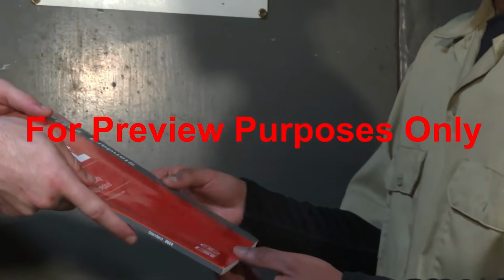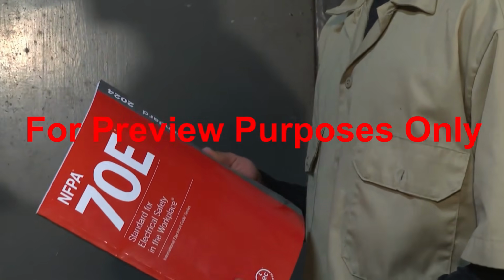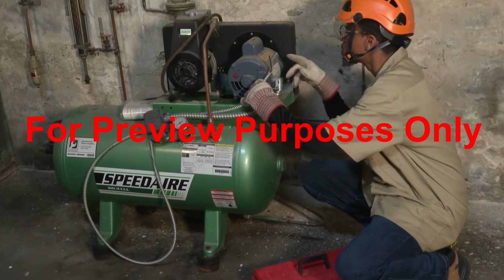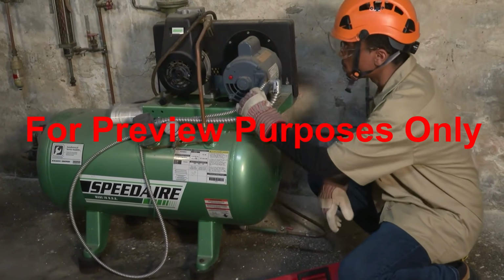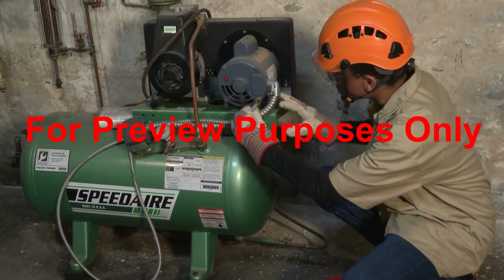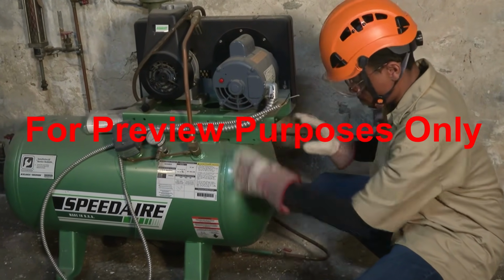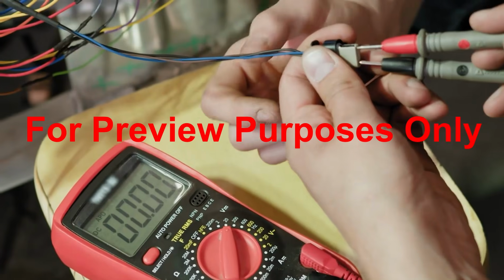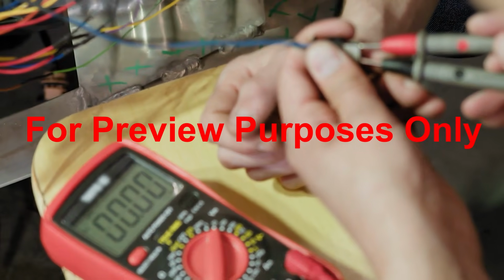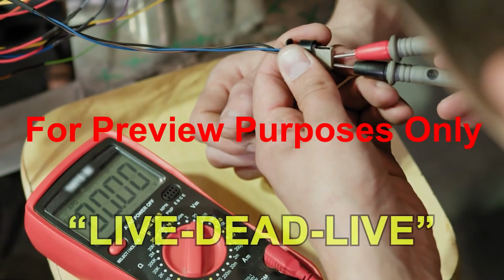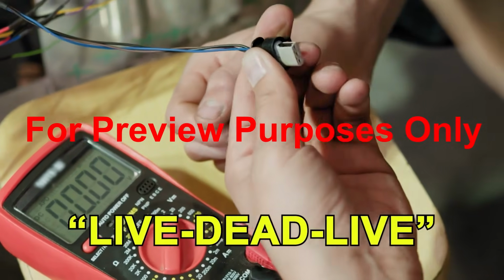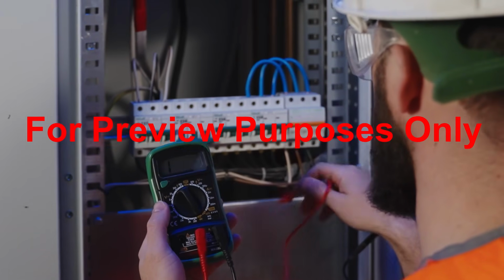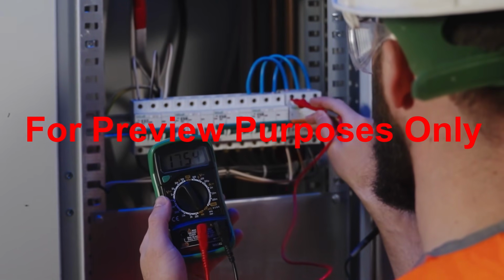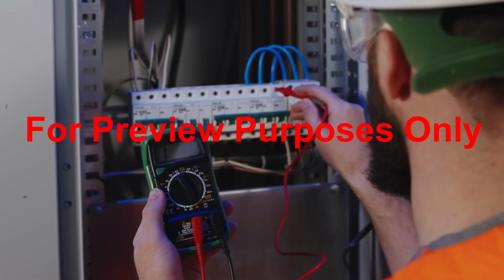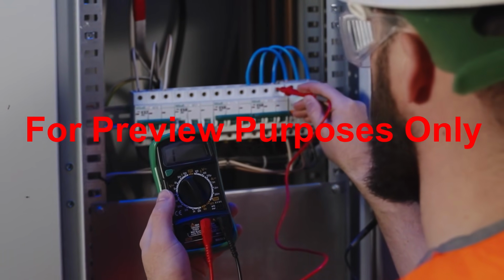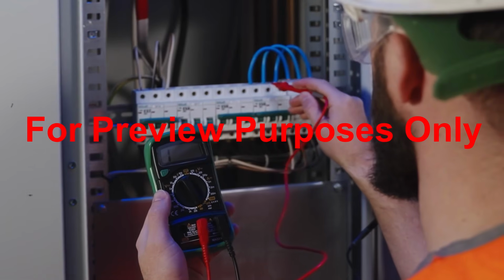The NFPA 70E standard also specifies that you should visually inspect all test instruments, equipment, and accessories for defects and damage before each use. One way to verify that test instruments are working properly is through the live-dead-live test. This involves attaching the instrument to a known source of voltage before and after you use it to test for the absence of voltage on the machinery that you're working with.